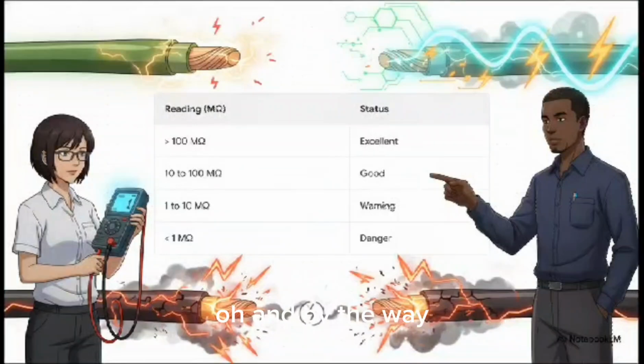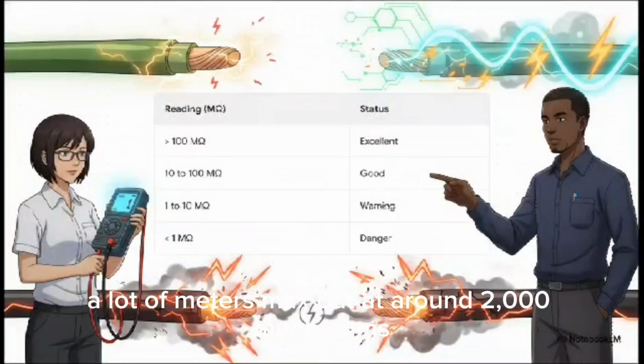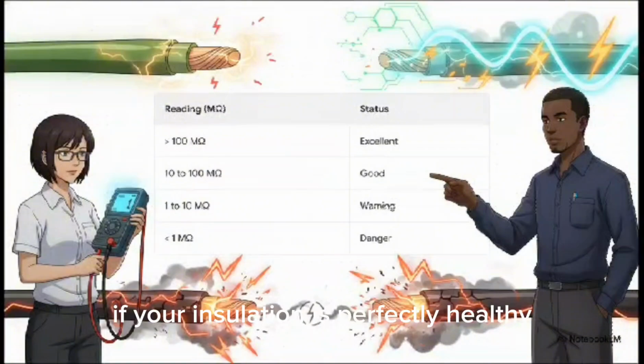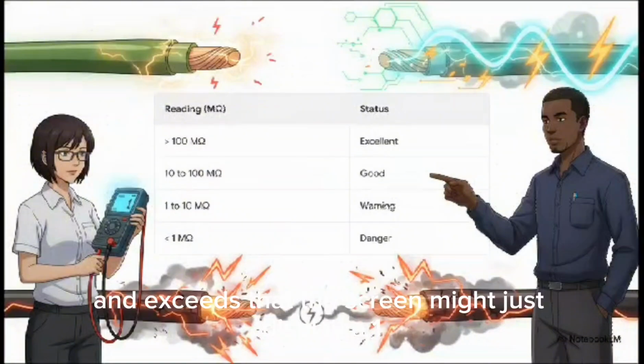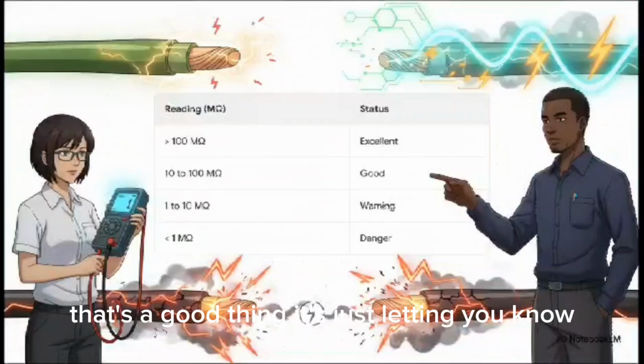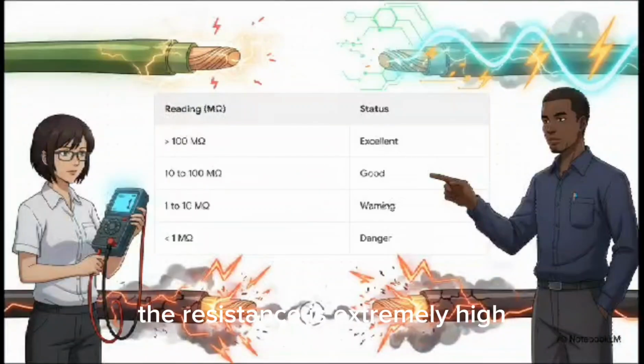Oh, and by the way, a lot of meters max out at around 2,000 megaohms. If your insulation is perfectly healthy and exceeds that, the screen might just display a 1. That's a good thing. It's just letting you know the resistance is extremely high and the wire is incredibly safe.